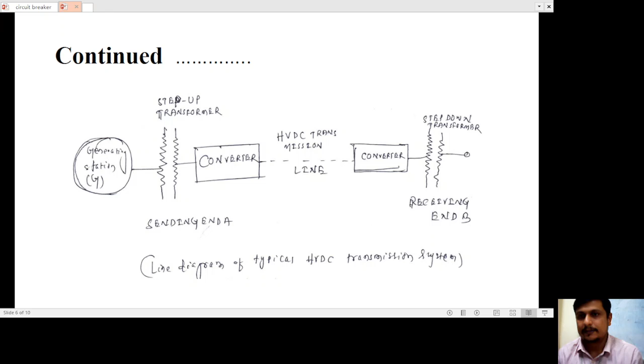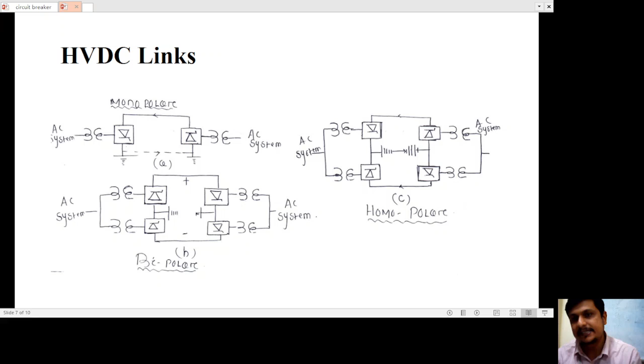These are the HVDC links. Basically, we are using three types of link in HVDC transmission. First one is the monopolar link, second one is the bipolar link, and third one is the homopolar link. In a monopolar link, only one conductor, having negative polarity, is present. In a bipolar link, two conductors of both negative and positive polarity are present. In a homopolar link, generally two conductors having the same polarity are present. That means generally both conductors have negative polarity.